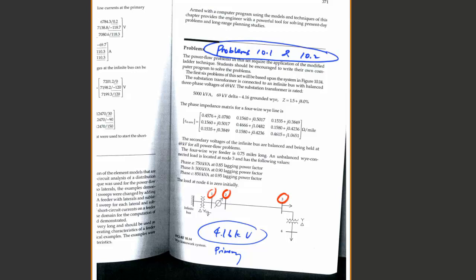So this is a 69 kV network with a substation transformer. This is a substation transformer, 5,000 kVA, so it's about 1,000 times the typical distribution transformer, in the delta grounded Y connected fashion, 69 kV to 4.16 kV. I think this is probably the 4.16 value that we have. And they give the phase impedance matrix with the 4 wires. This is actually already reduced into a 3 by 3 matrix, so this is good to go, except that you might have to multiply it by the distance you need.